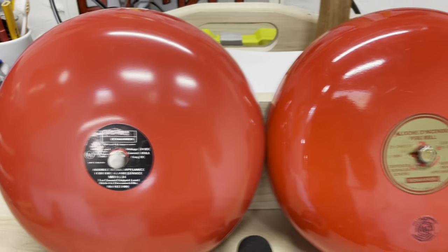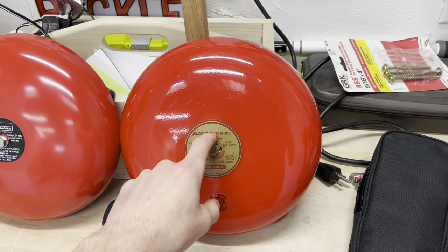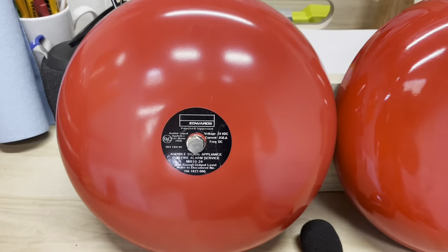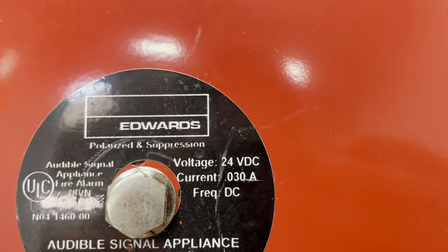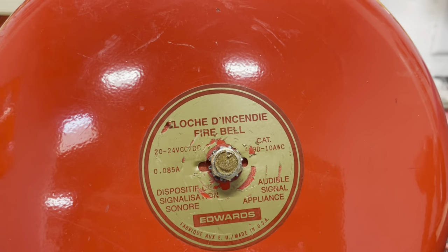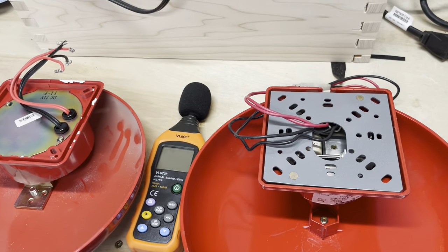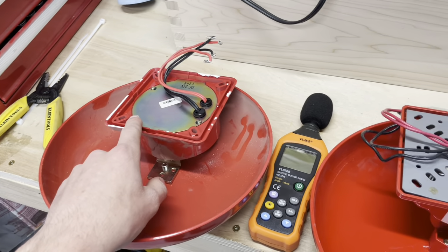Obviously, this is a motor bell versus a vibrating bell. I like the vibrating bell better, I think it sounds better, but that's just a bias I have — I gotta put that aside. Already off the bat, advantage to the motor bell, the MB10-24: if you look at the current, it's only 0.030 of an amp, versus this one is 0.085 amp, so it's more current draw for the vibrating bell. Also, the motor bell is definitely an easier bell to install.